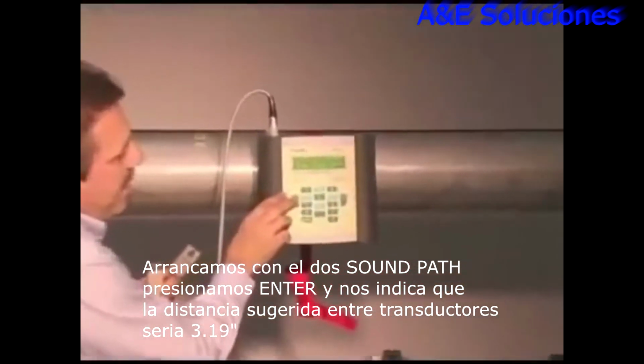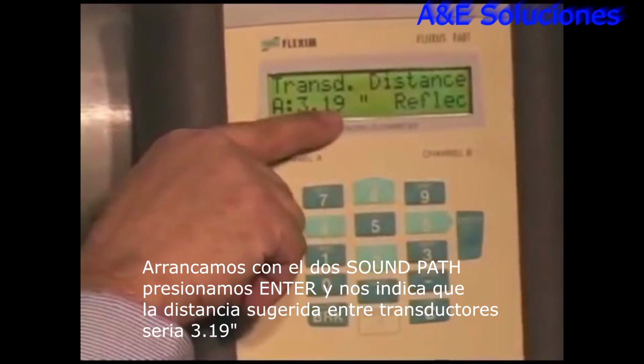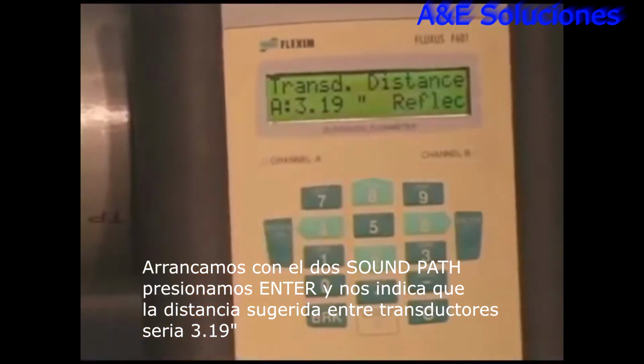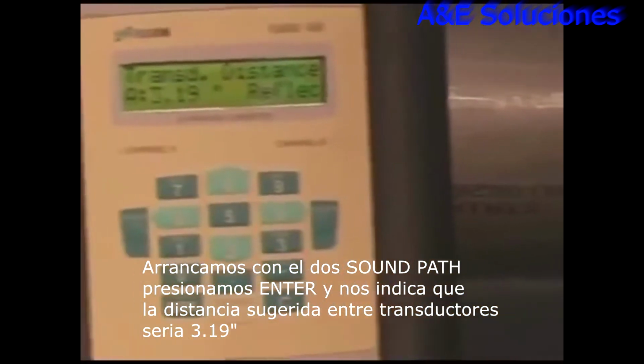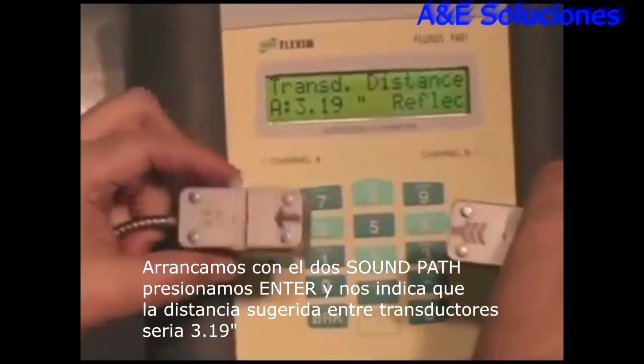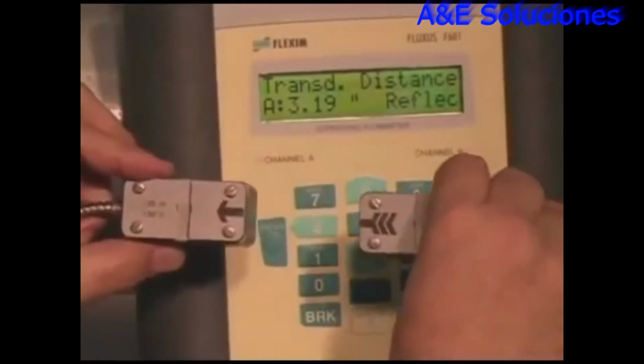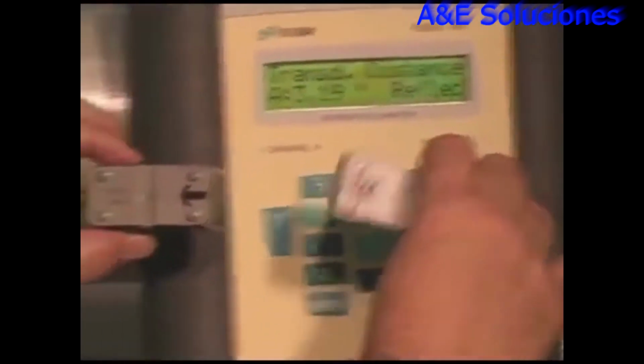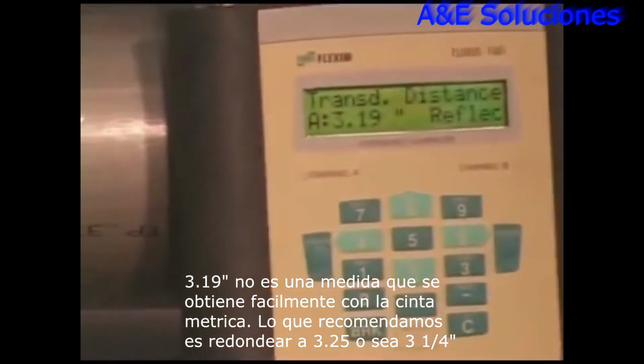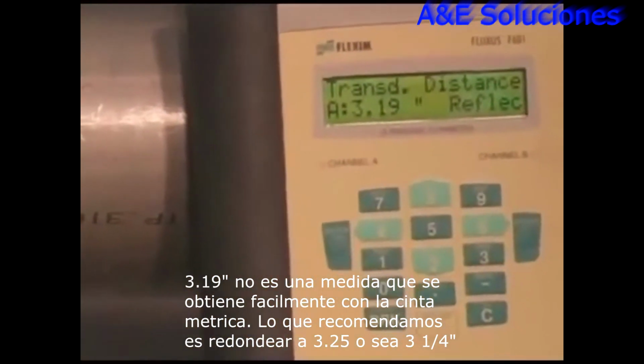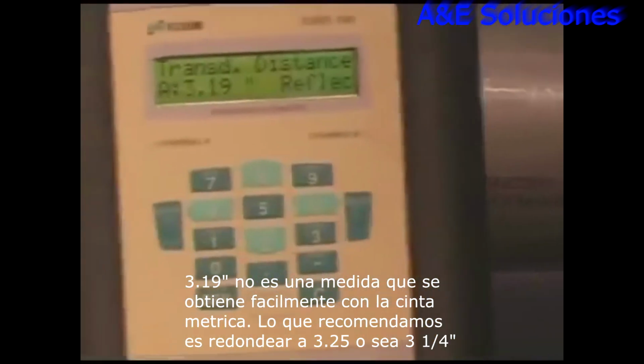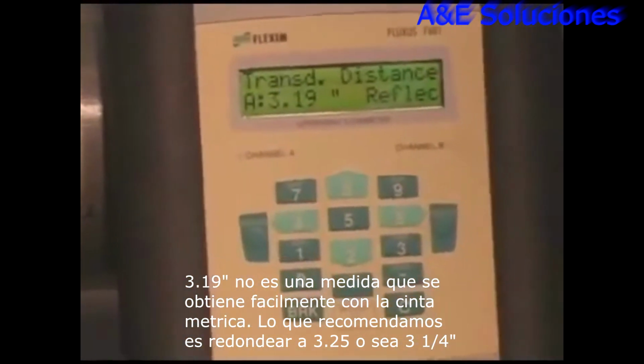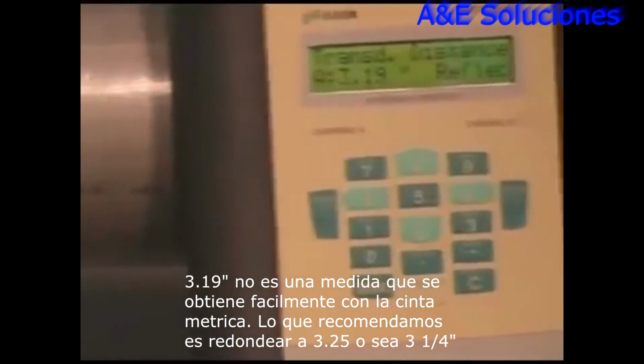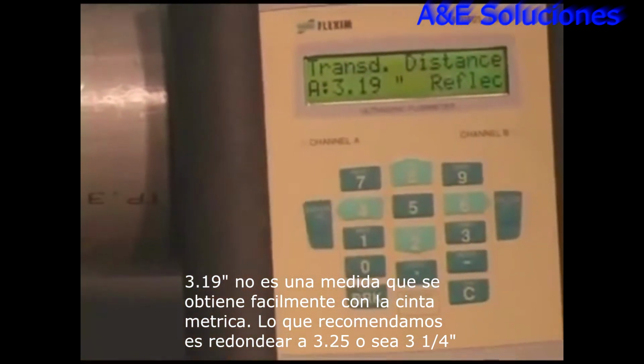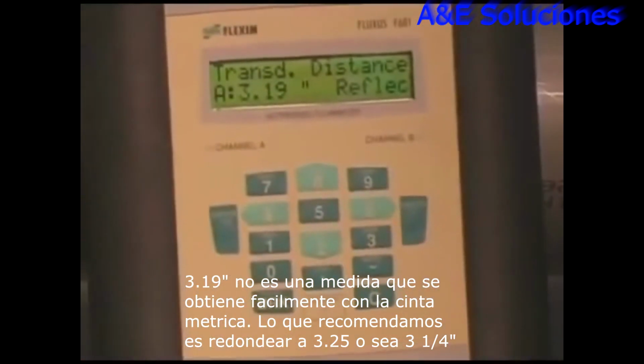Hit enter. Now it gives us a recommended spacing distance, and it's saying 3.19 inches reflect mount. That's the distance that we're going to set these transducers apart from one another. And so we'll start off, we'll mount one up on the pipe, and then we'll measure the other one out. Now 3.19 inches is not an easy distance to measure off the tape measure. What we recommend you do, and it's quite acceptable, is to average that off to plus or minus a quarter inch. So the 3.19, I'm going to average off to 3.25.